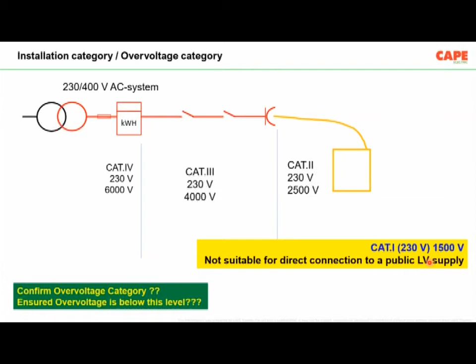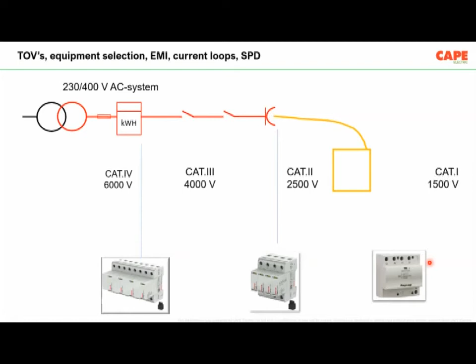Then the second part, which is influencing the protection of electronics, is temporary overvoltages, the equipment selection, the electromagnetic EMI current loops, and SPDs or filters. What is current loop or temporary overvoltage? Temporary overvoltage in the sense, in case I am just showing you a picture of a transformer, there is a fault, the indication of a fault. Here I am moving the cursor, a fault on the HT side of the transformer.